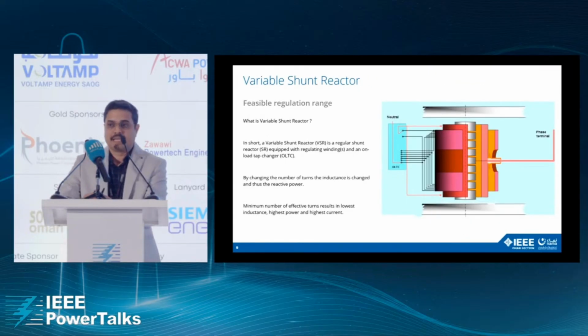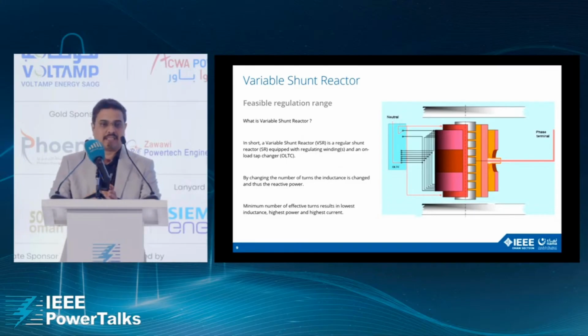Now, what is a variable shunt reactor? A variable shunt reactor is simple. It's a reactor with an on-load tap changer. So, it has a tap changer connected to its winding. It keeps on changing the number of turns with a smooth flow of inductance.